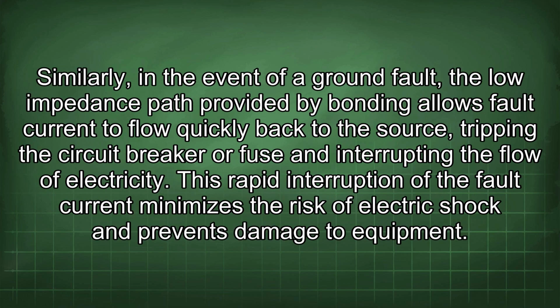Similarly, in the event of a ground fault, the low impedance path provided by bonding allows fault current to flow quickly back to the source, tripping the circuit breaker or fuse and interrupting the flow of electricity. This rapid interruption of the fault current minimizes the risk of electric shock and prevents damage to equipment.